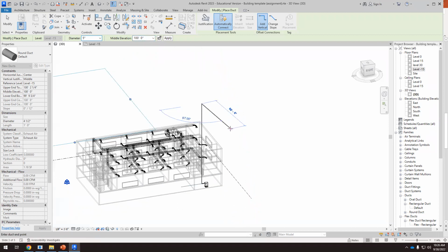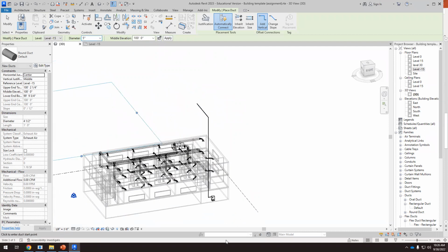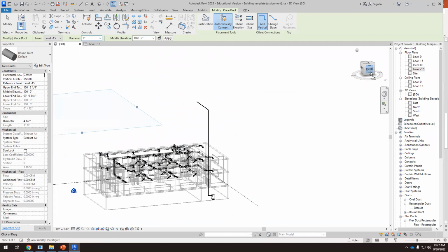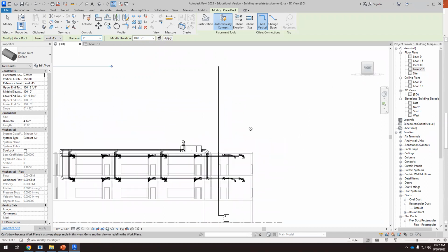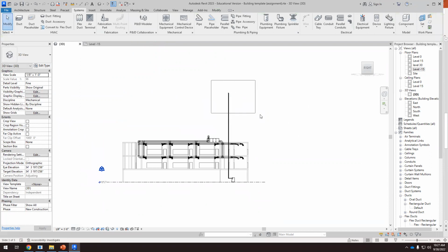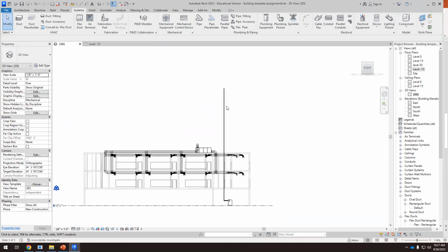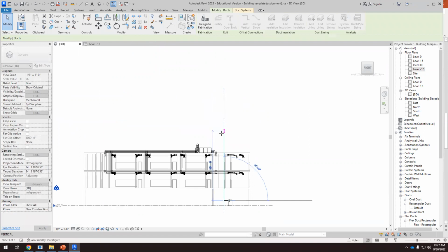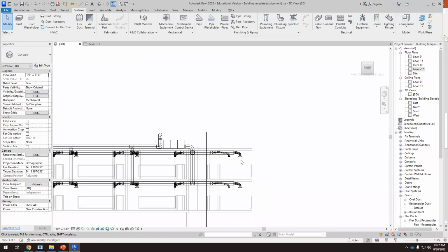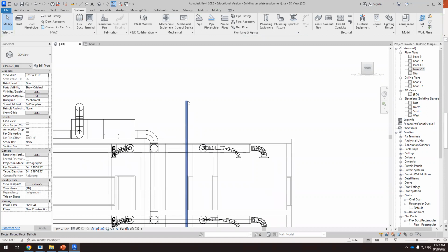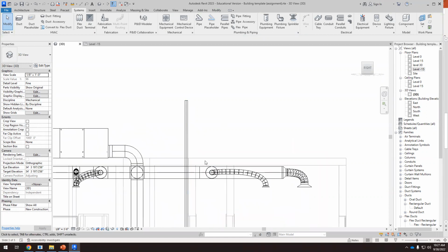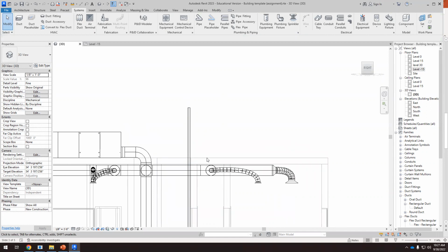And you see that we have a vertical duct. And then we need another horizontal, and we can escape. And we have this. It's too high, so I need to get rid of the horizontal part, and then I can drag this down. Okay, and this should be at least 7 feet, the distance between the top of the chimney up to the roof level.